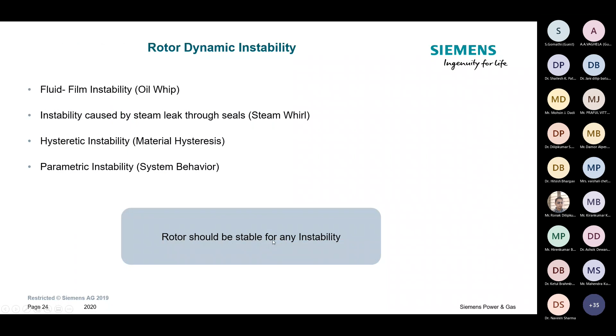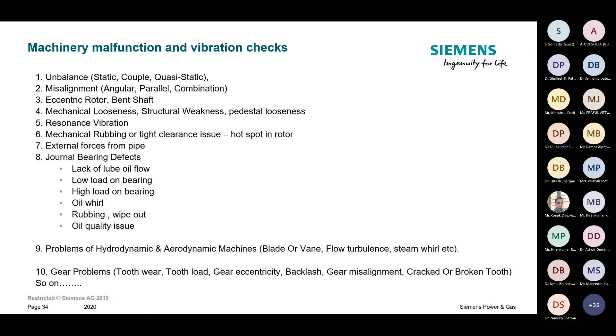And aerodynamics within the blade is also getting forced by steam and other things. So flow turbulence and flow separations within the steam excite the blade, and the blade starts vibrating, and as a result you see vibration in the rotor. Sometimes in industrial applications the steam turbine is connected with a gearbox. So the gearbox has its own problems, because wear and tear is there. They sometimes crack, backlash happens, misalignment happens. So those kinds of vibrations are also there. So this is not a one-item list. There are, as I said, 30 or 40 or more possible reasons you have to work on.